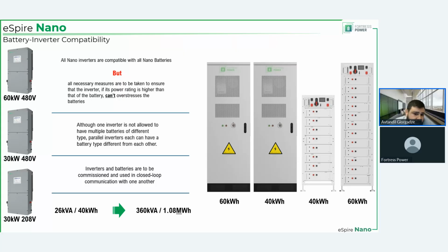So 360 kVA comes from 6 60 kVA or 60 kilowatt 480 volt inverters, and 1.08 megawatt hours comes from 60 kilowatt hour batteries connected to each of these inverters. So you have 6 inverters, each one with 3 batteries. You have 18 batteries, 18 times 60, that's 1.08. Well, 18 times 60 is not 1.08, it's 1080. But if you convert it to megawatt hours, it's 1.08 megawatt hours.